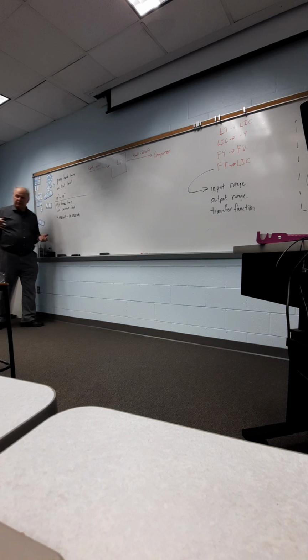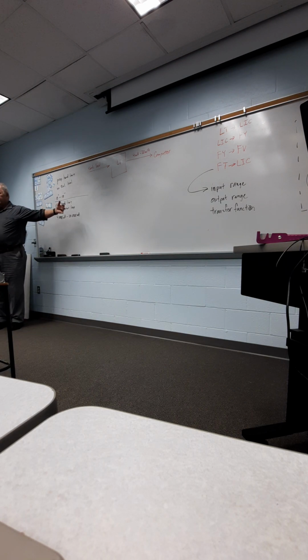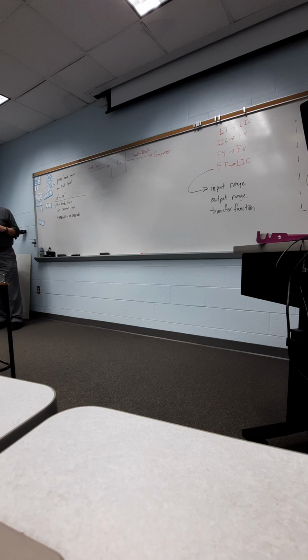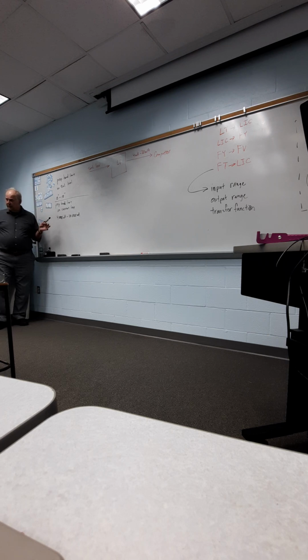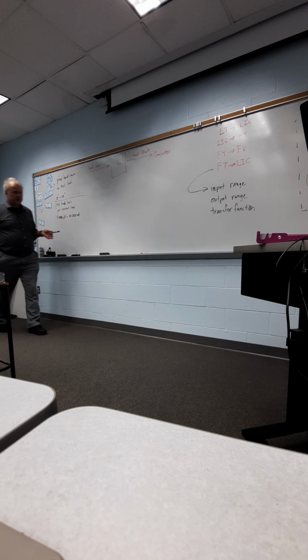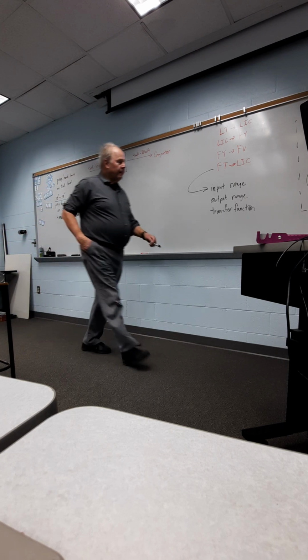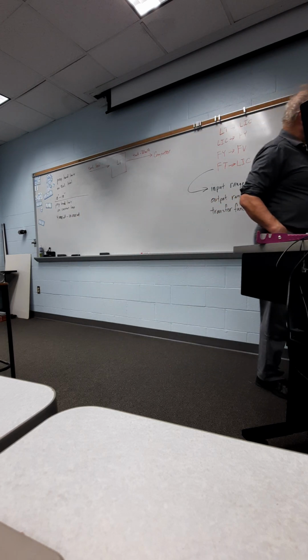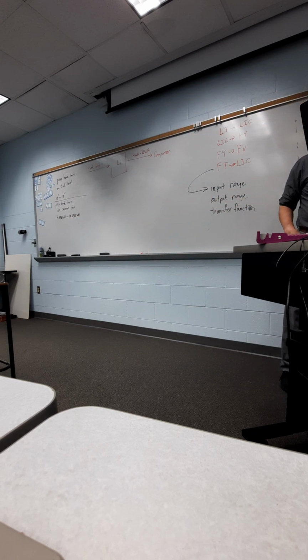First thing you start reading proportional bands, you say, well, gee, the wider the better. Why can't I cover the world? Theoretically, hypothetically, if you have no limitations to your abilities to handle such things, there is no reason to limit anything. But we do have practical limits here on proportional band. One of them here is physical. I don't want to necessarily measure beyond 10 inches, because beyond 10 inches, I'm in trouble.